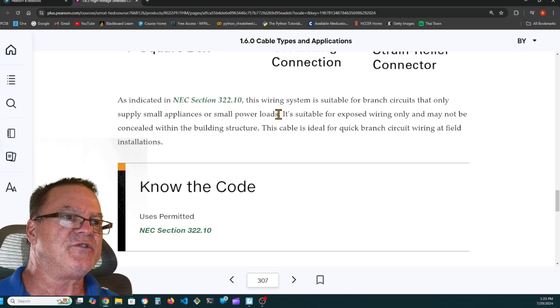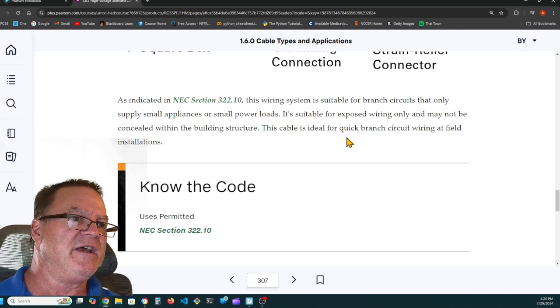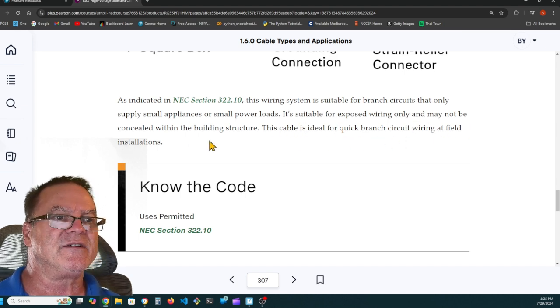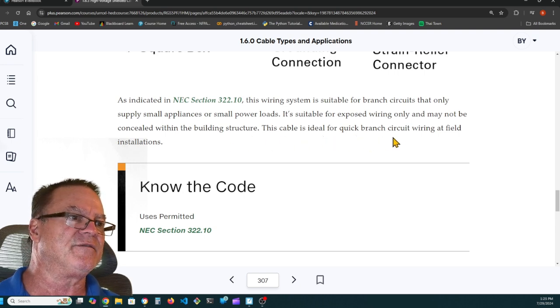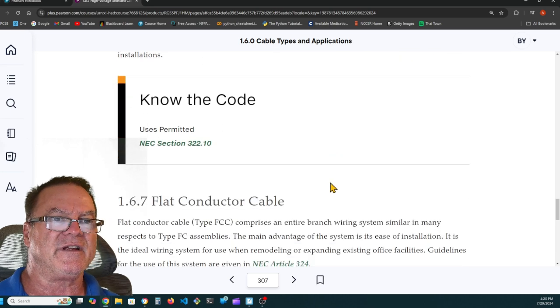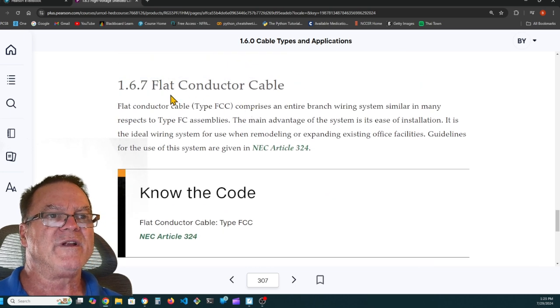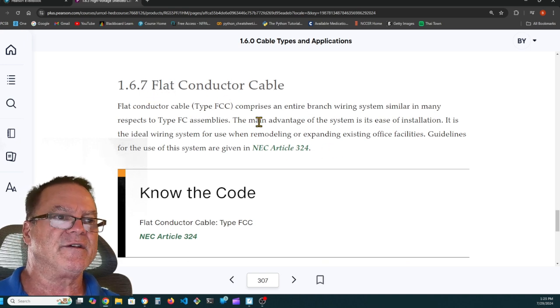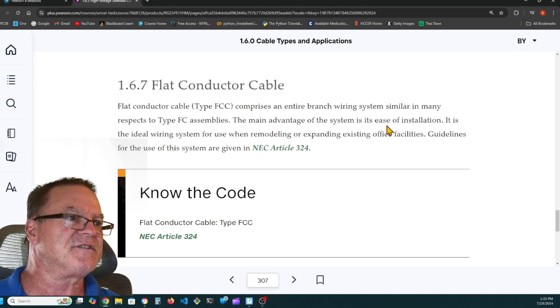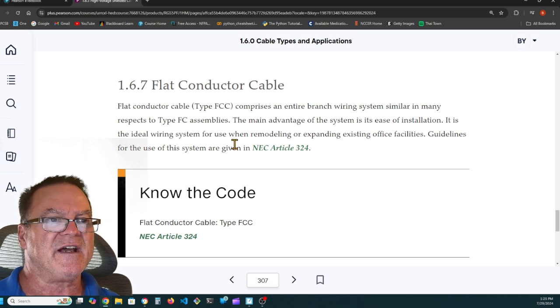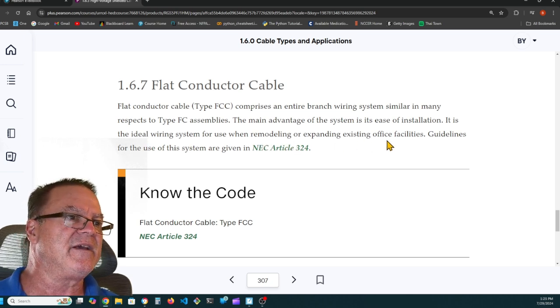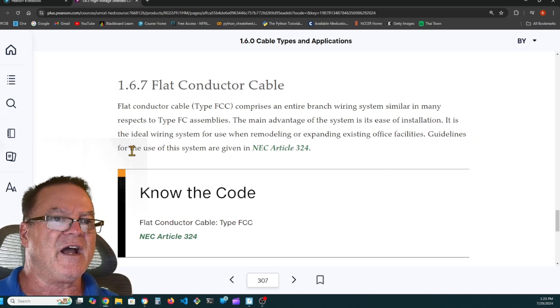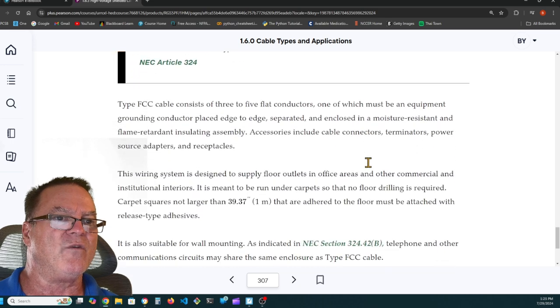As indicated in section 322.10, the wiring system is suitable for branch circuits that only supply small appliances or small power loads. It's suitable for exposed wiring only and may not be concealed within the building structure. This cable is ideal for quick branch circuit wiring at field installations. 1.6.7 Flat conductor cable. Flat conductor cable comprises an entire branch wiring system similar in many respects to type FC assemblies. The main advantage of the system is the ease of installation. It's the ideal wiring system for use when remodeling or expanding existing office facilities. Guidelines for the use of this system are given in Article 324.